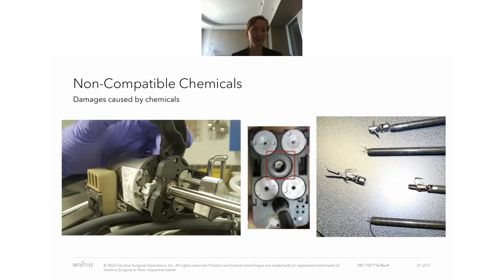Now here you can see some examples of what the wrong chemical could do. The first two examples are actually due to rinse aid. You can see how the plastic is cracked, and in the second picture, how the input disc has broken off. So if you see this in your facility, this could be an indication that there is a chemical issue and it's worth looking into. And on the right-hand side, you can see some broken tips with frayed cables, and that was due to the use of hydrogen peroxide. That can have an effect on the instruments like this.